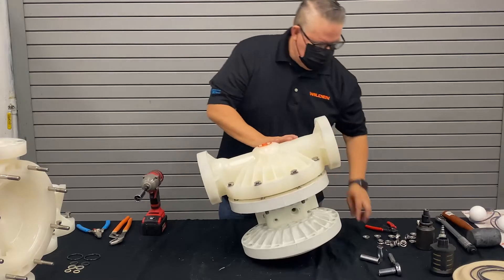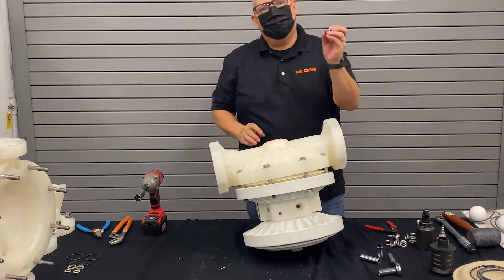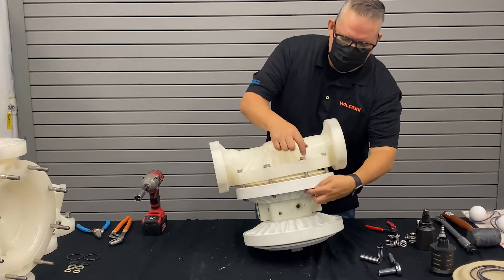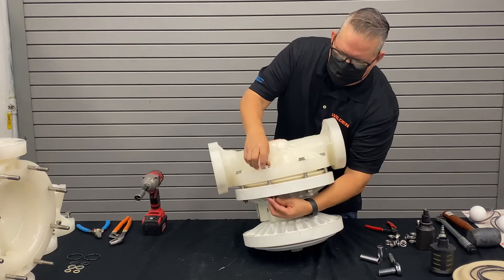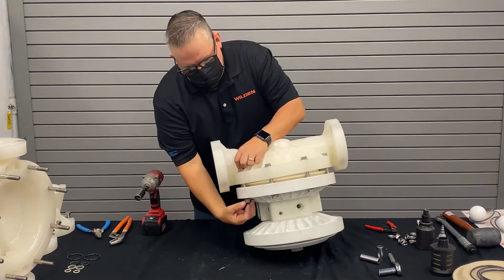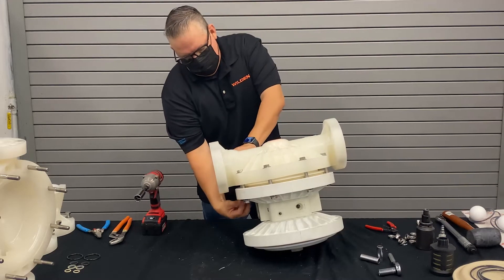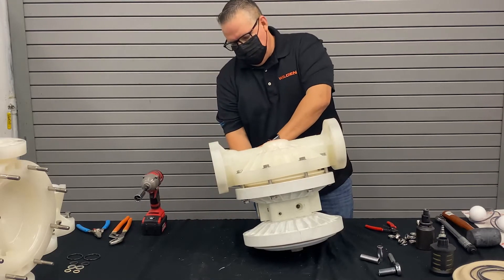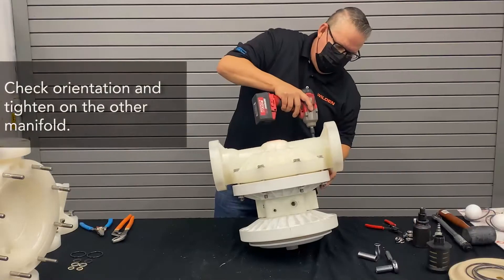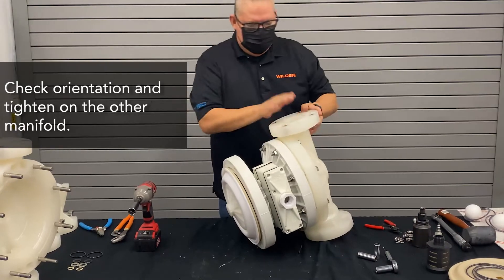Once we get the liquid chambers in place, we're going to get all those fasteners started. Wilden uses a flanged hex nut — it's a hex nut with a serrated flange. The serrated edge grabs into the plastic so that when you tighten it up, you don't really have to keep a wrench on the other side. It makes assembly a lot easier. Once we get all these started, we'll go ahead and run them down. Once tightened, you can go ahead and get to the other side and tighten up that other manifold.